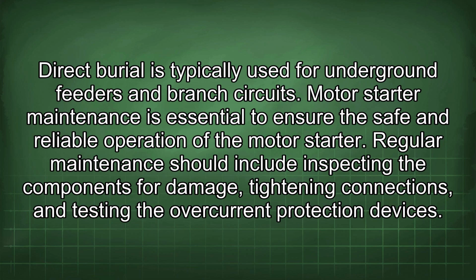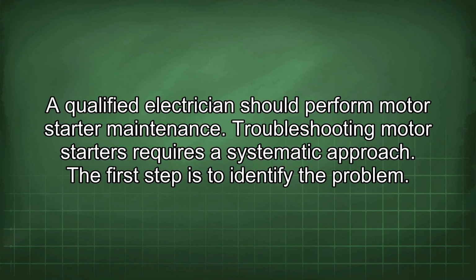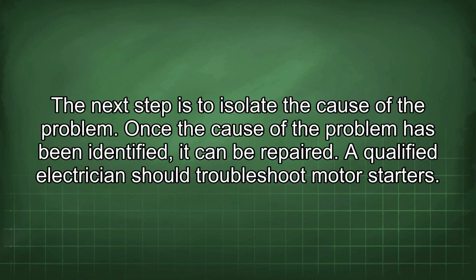Motor starter maintenance is essential to ensure the safe and reliable operation of the motor starter. Regular maintenance should include inspecting the components for damage, tightening connections, and testing the overcurrent protection devices. A qualified electrician should perform motor starter maintenance. Troubleshooting motor starters requires a systematic approach. The first step is to identify the problem. The next step is to isolate the cause of the problem. Once the cause of the problem has been identified, it can be repaired. A qualified electrician should troubleshoot motor starters.